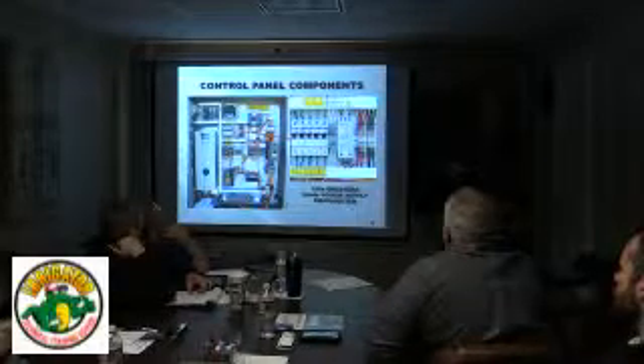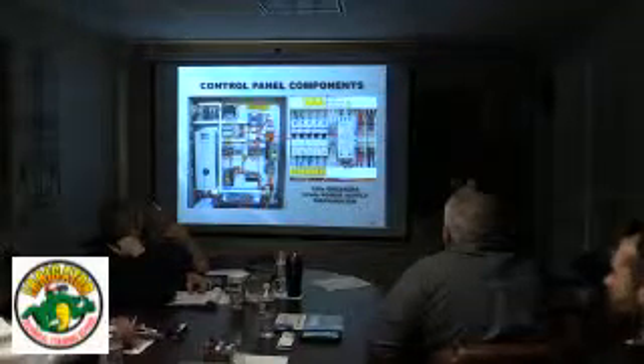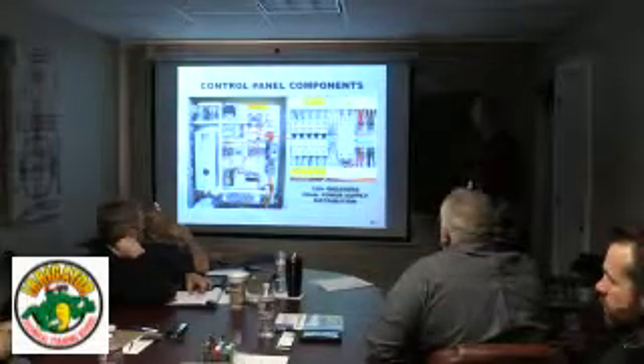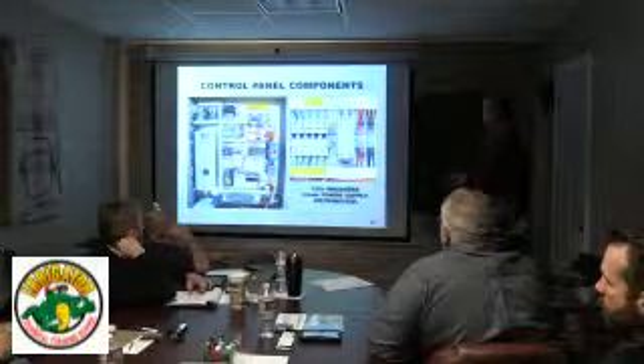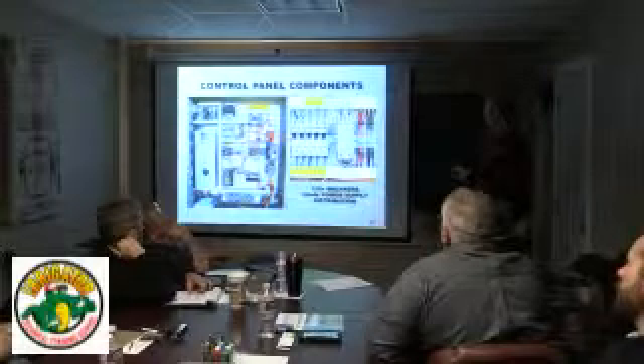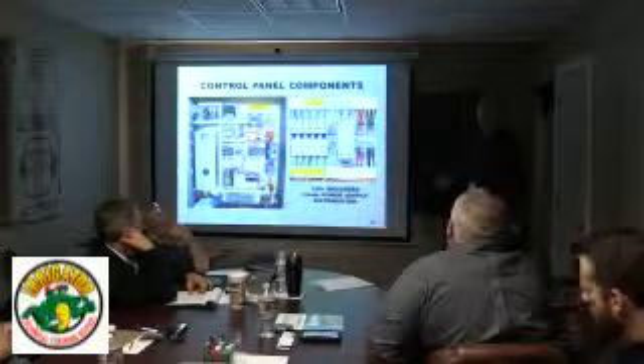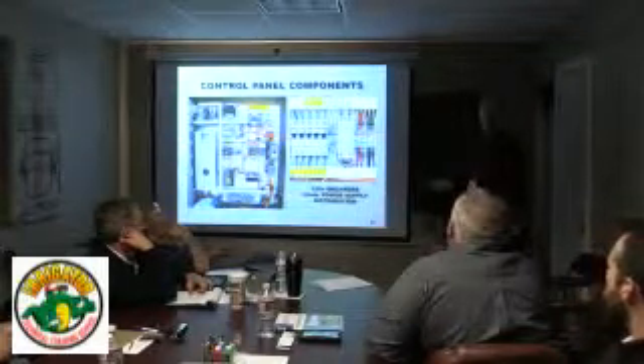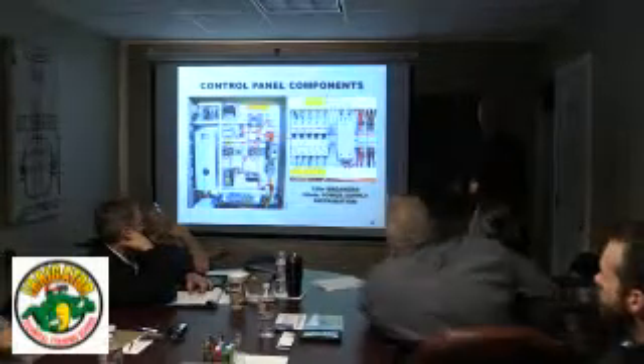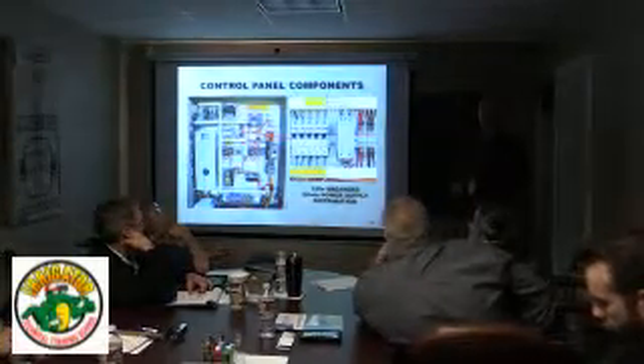Our 120 neutral from the transformer just comes to this distribution block. That's all it is. That just means that we can plug in a lot of different 120 volt neutrals to wherever they need to go. We also have one for 24 volt DC and the negative. It's kind of hard to see, but all of our 24 volt DC is a black with a red stripe. So if it's black without a red stripe, it's probably 120 volt hot. If it's black with a red stripe, it's the negative minus of the 24 volt DC power supply.